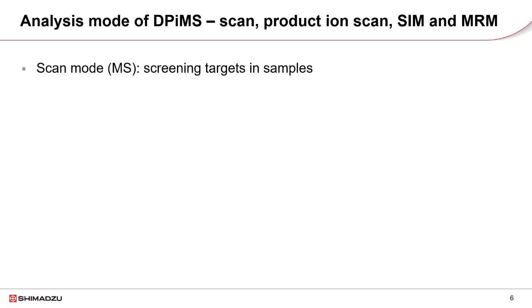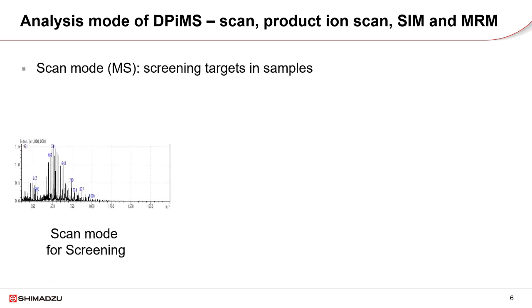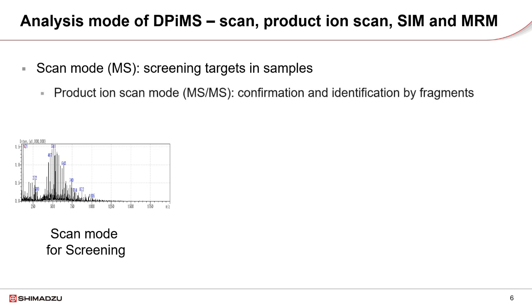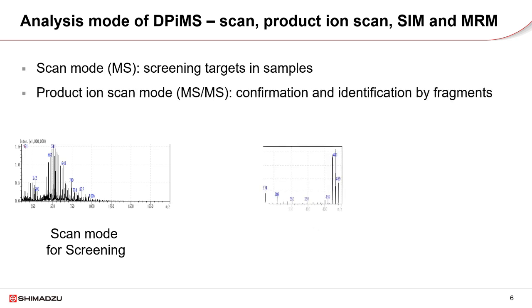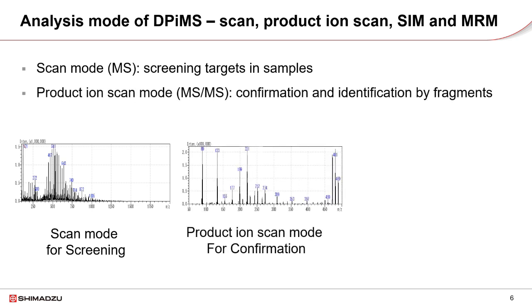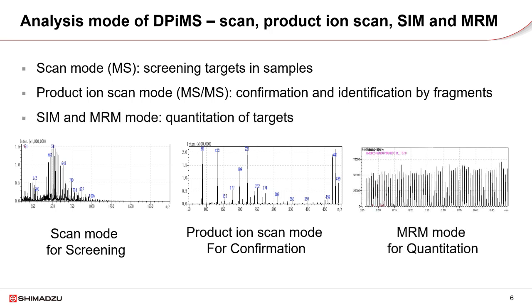The analysis modes of DPI-MS include scan mode, product ion scan mode, SIM mode, and MRM mode, depending on the analysis purpose. Scan and product ion scan methods are used for detection, confirmation, and identification of compounds, while SIM and MRM methods are used for quantitation.